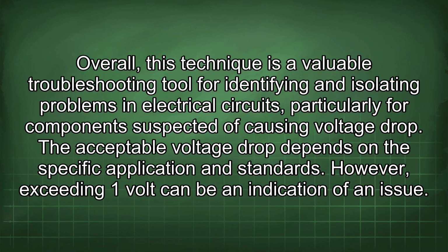Overall, this technique is a valuable troubleshooting tool for identifying and isolating problems in electrical circuits, particularly for components suspected of causing voltage drop. The acceptable voltage drop depends on the specific application and standards. However, exceeding 1 volt can be an indication of an issue.